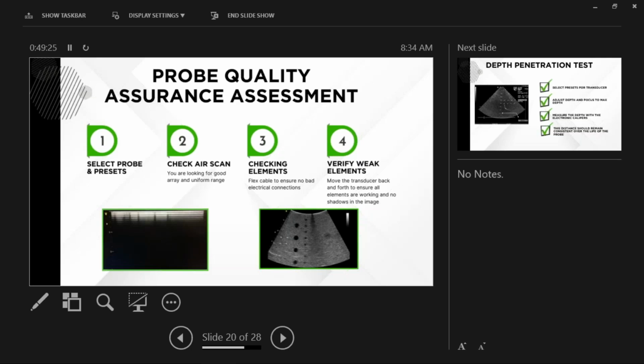Sometimes you plug in a transducer, you'll see a little blemish or dropout. It could just be the pins. So I'll come over here, give the connector a little wiggle, make sure they rub against each other, and then you may or may not see that disappear. So the first test would be an air scan. That usually will give you an indication right away whether or not the transducer is having an issue.